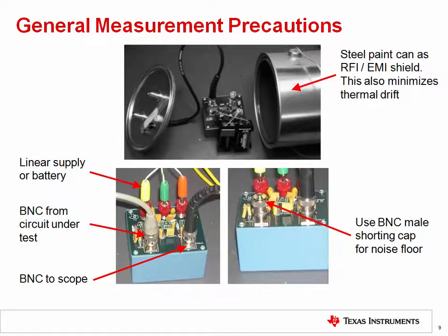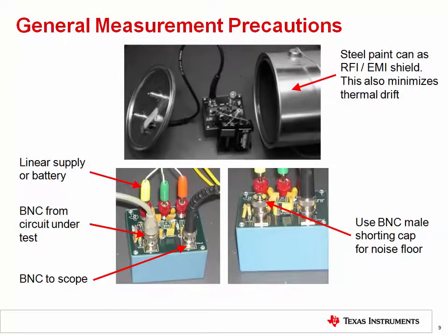In addition to the proper configuration of oscilloscopes and spectrum analyzers, other aspects of your test setup can also have an impact on noise measurement quality. Use a well shielded and grounded environment, making sure that the shield is grounded and that any gaps are minimized — copper and steel are good choices, and a modified steel paint can is often used as a shield. Make all circuit connections directly with BNC cables, use batteries or linear power supplies for the lowest noise power, and don't leave unterminated or floating inputs on your devices. The goal of this testing is to measure intrinsic noise, so these precautions are focused on eliminating sources of extrinsic noise.